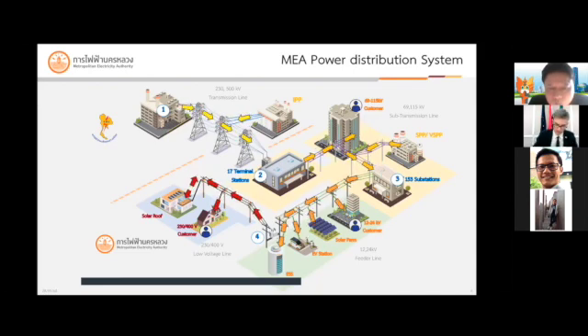Along the way, the grid can receive power from the solar farm, supply the power to EV stations, and charge or discharge ESS batteries. Then, distribution transformer, number 4, will step down the voltage to 230/400 volt, supplying the power to the resident customers. Some houses installing solar PV rooftop can sell the power back to MEA depending on the contract.